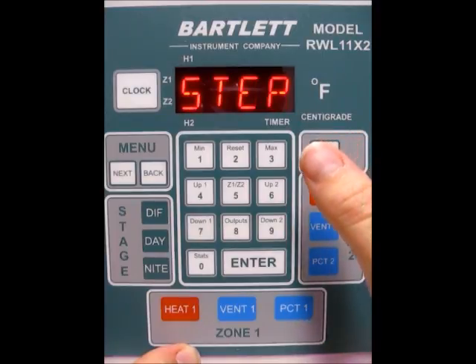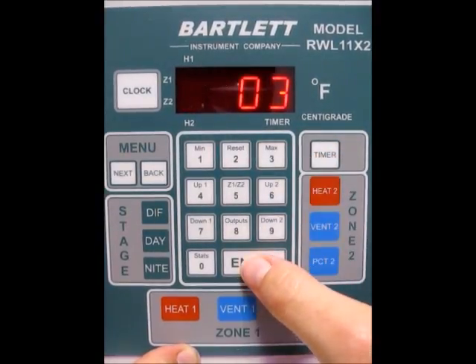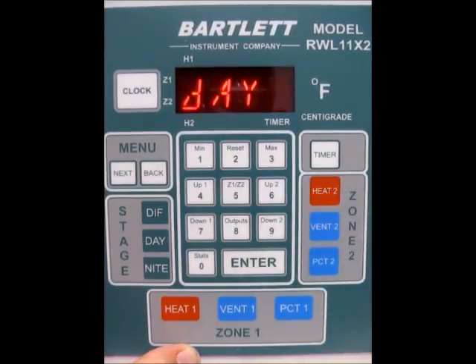Now it's asking you for your step size. So we're going to do a step size of 3. Press 3 and press Enter. So right now our target temperature is 75. So that means that Vent 1 should come on at 78. So we're not quite there, but if it were to go to 78 degrees in the greenhouse, Vent 1 should go ahead and start opening.